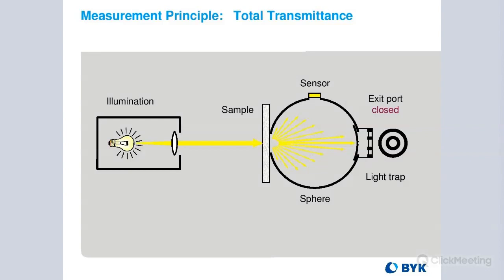The sphere is a white-coated sphere, made so that when the light hits it — whether it's direct or diffuse transmittance — it all bounces around the inside of this white-coated sphere and is captured by the sensor. This is how total transmittance is measured, given as a percentage relative to the reading in open air. Open air is measured at 100%. If your sample measures at 70%, that means that 70% of the light is getting through as was getting through with open air.